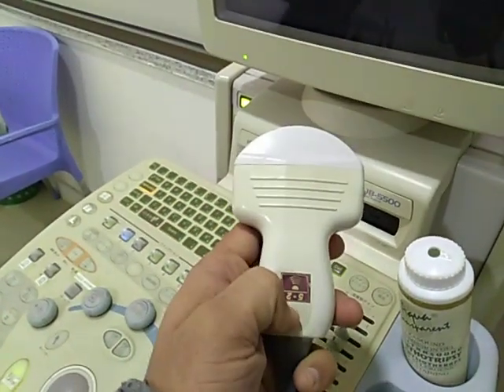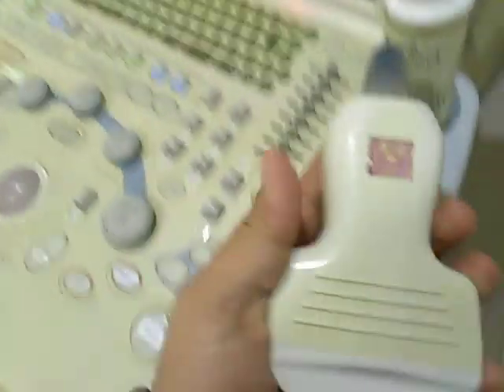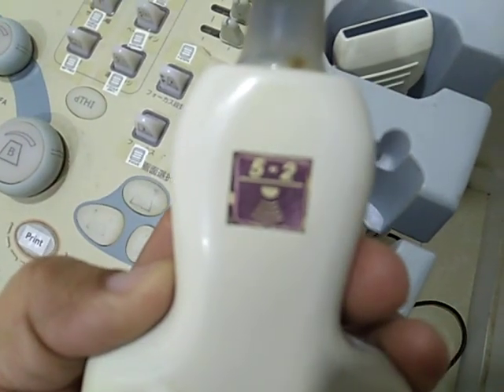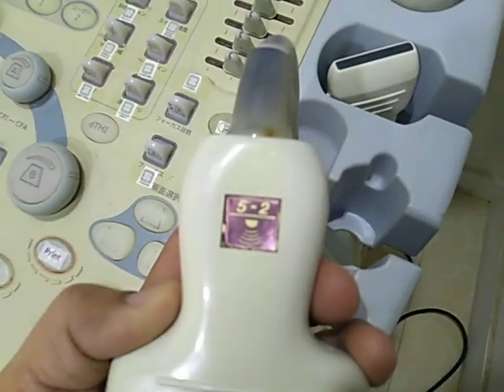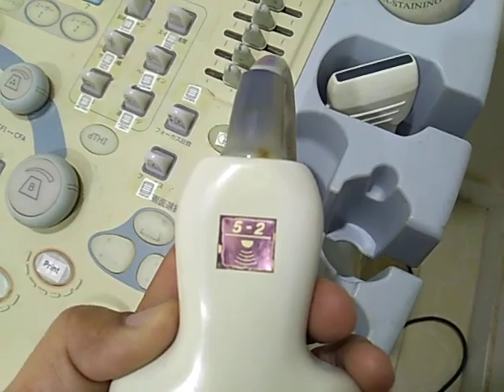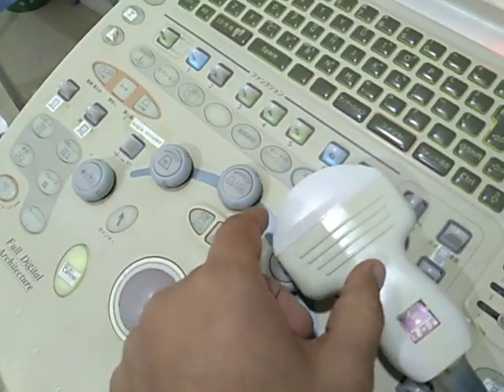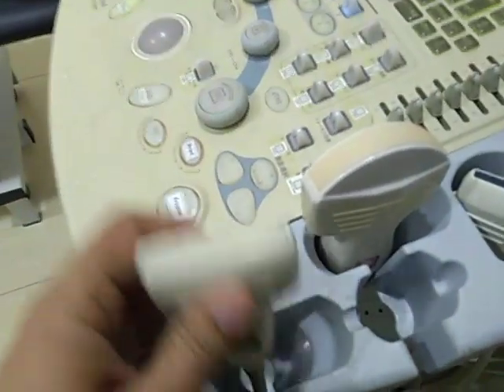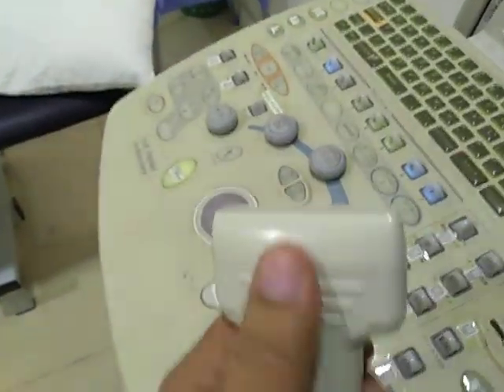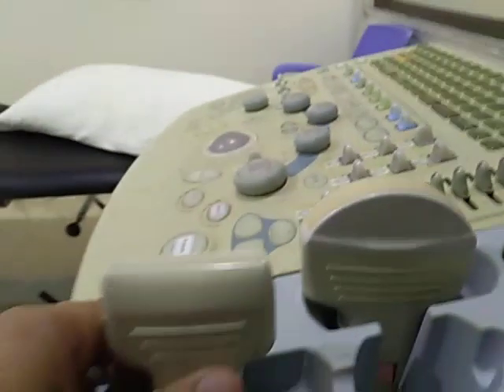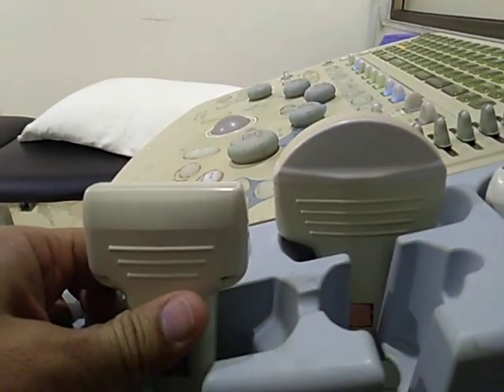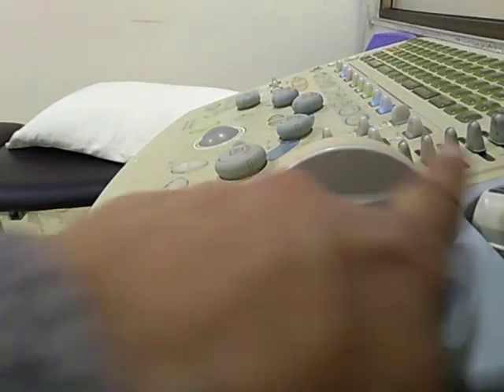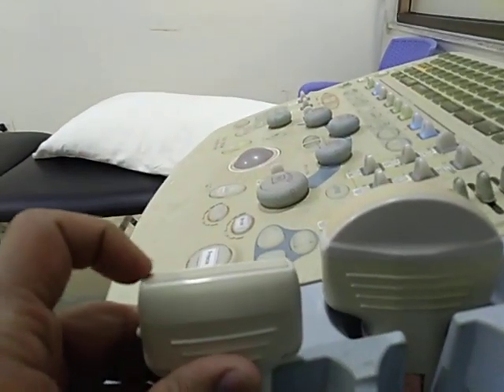So this is the probe that they use. So you can see this is from 2 to 5 megahertz. Let me make it very clear for you guys. So this is from 2 to 5 megahertz, and basically this is a curvilinear. You can see the interface or the head of the probe is curved. But if you compare it with the other probe, which we most commonly use, this is called the linear probe. So yeah, you can see from this view that this is the curvilinear. It's curved on top, and this is a linear probe.